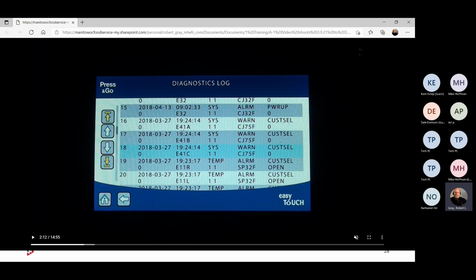So here we see an E41. An E41 is an insufficient power supply, the 3-phase power supply. The letter after the E41 is a designator of what phase is insufficient. So if you have an E41A error code coming in and it's on your dispatch paperwork, the first thing you're going to do when you get on site is go into the diagnostic log. You're going to scroll down and find the most current E41, and look to see if A, B, and C for each phase are in a row with all the same date and timestamp, like you're seeing here.